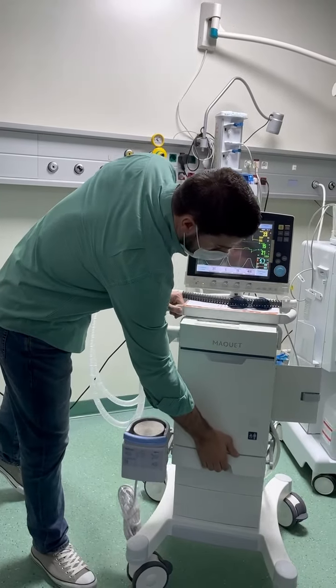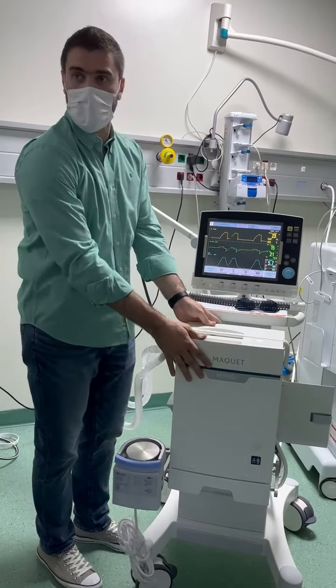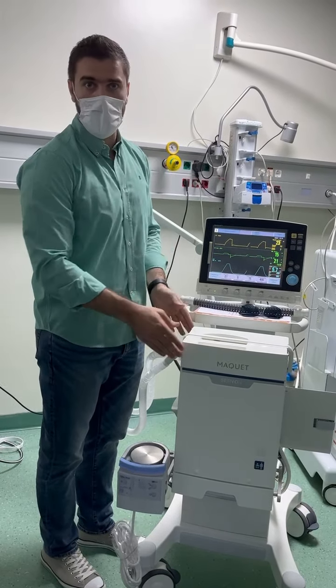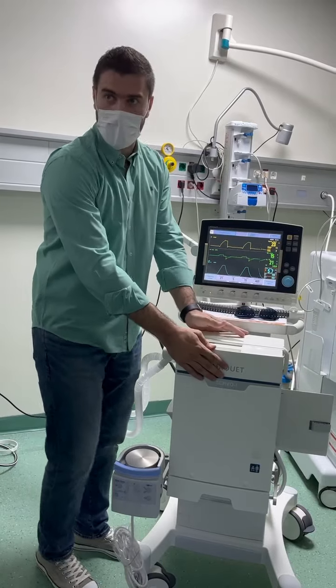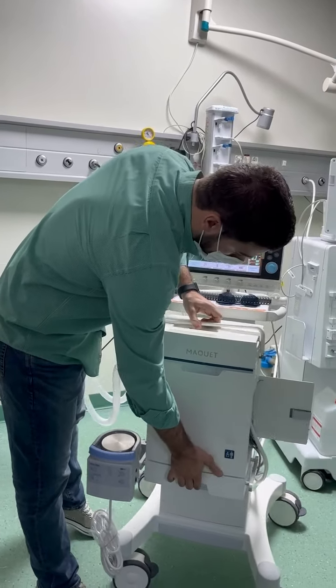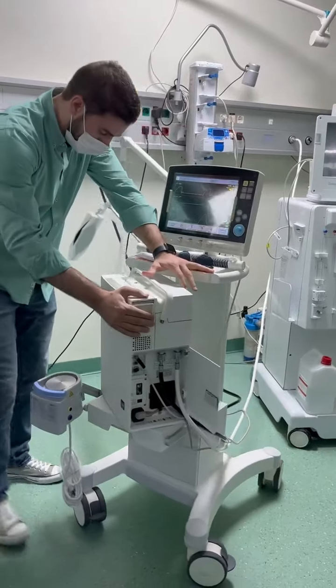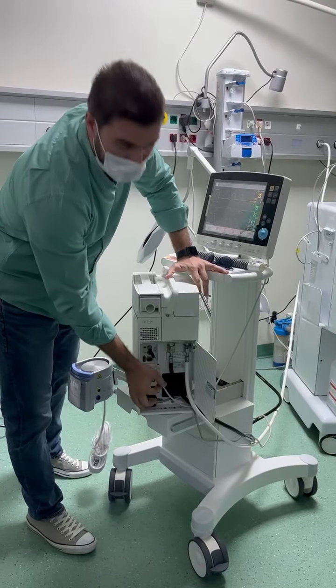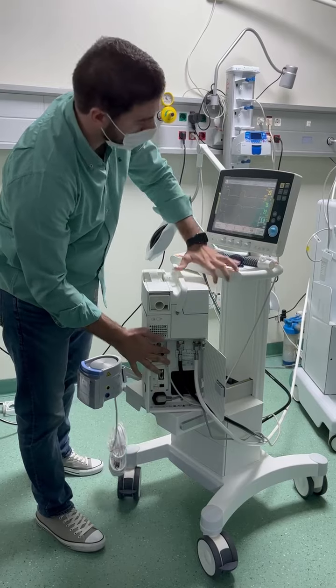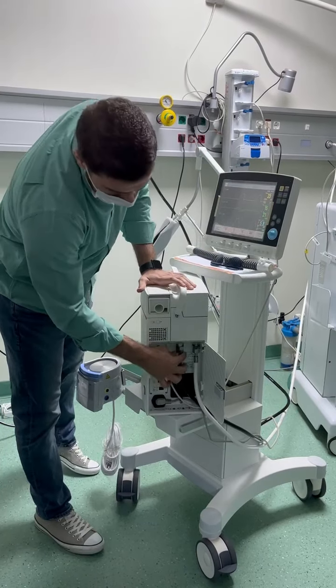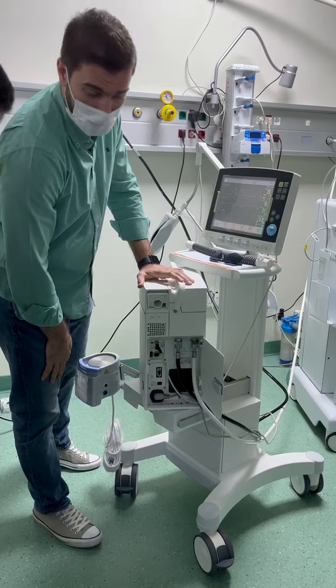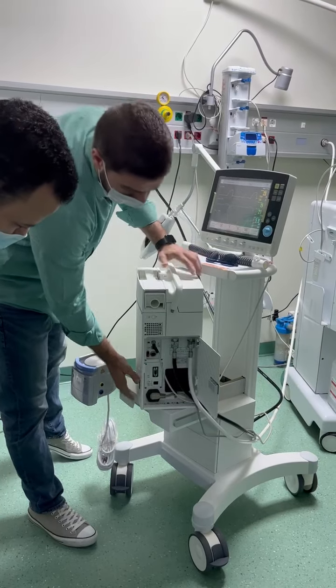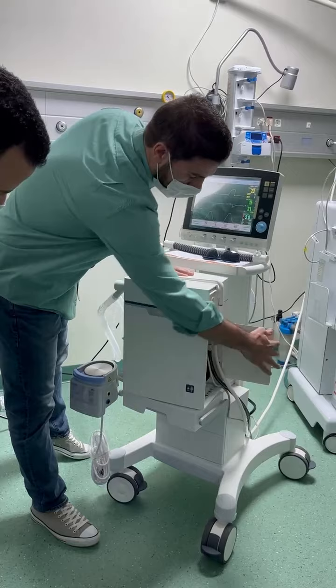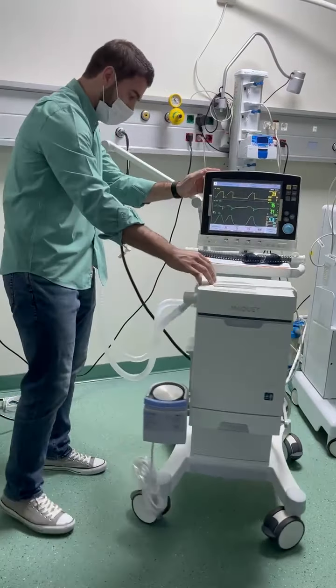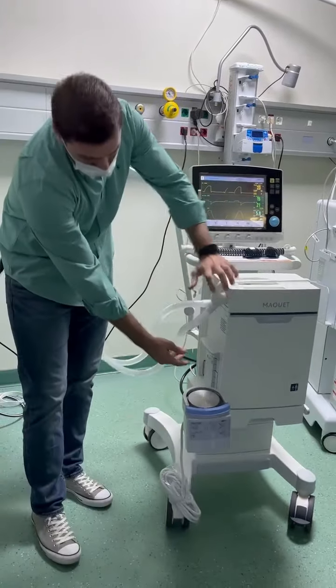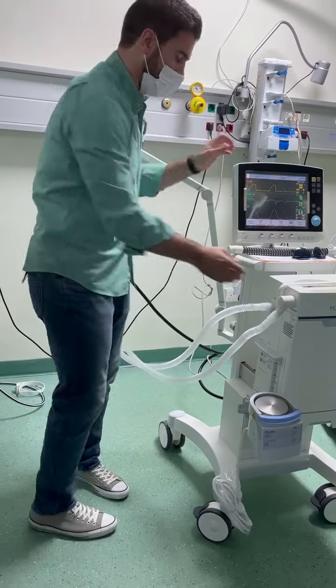Here we have the base unit. This is called a base unit, the heart of the ventilator. All the process or the gas module are inside. Right. What do you have on the base unit? From this side, if you can see, this is called the control cable. It is connected to the screen. Okay, gas inlet, air and oxygen, and power. It's very simple from this side. From the other side, we also have expansion slots or module slots, if you can see it all.